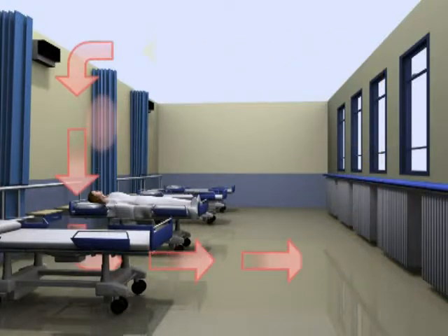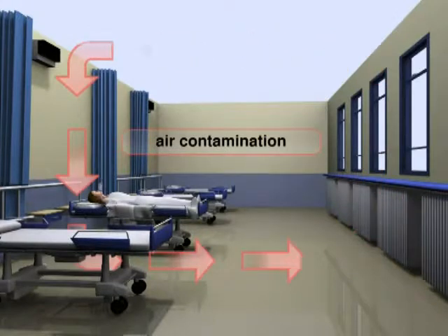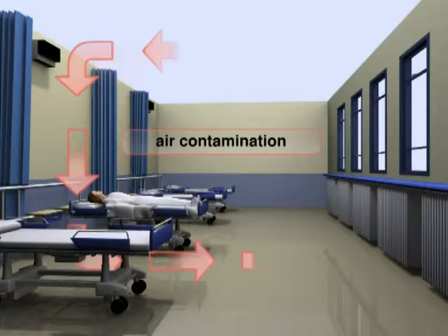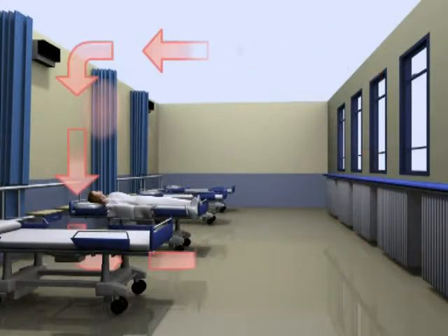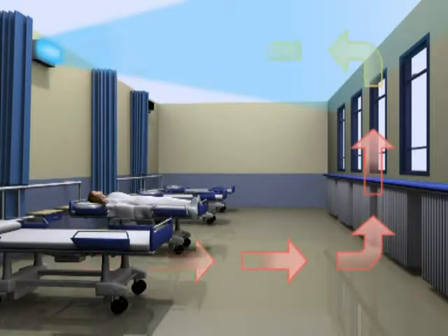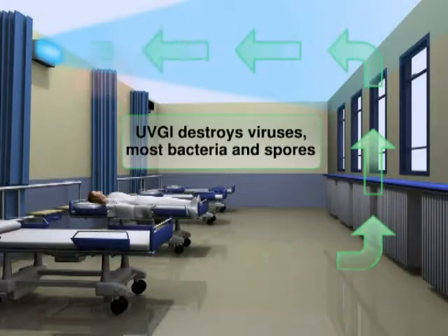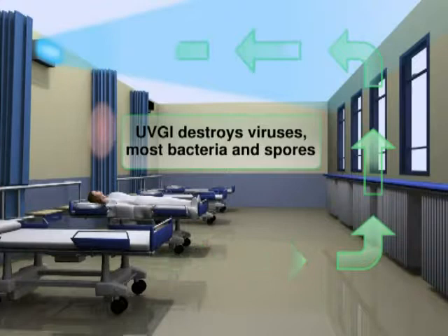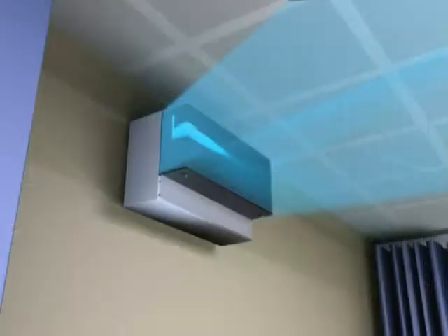Because of this, an air quality will be created where the level of pollution is so low, the risk of infection will be drastically diminished. The lamps produce light with a 254 nm wavelength. This radiation deactivates bacteria, viruses and other microorganisms. The DNA structure is destroyed in such a way that the cells can no longer multiply. The process is clean because it does not produce dangerous by-products.